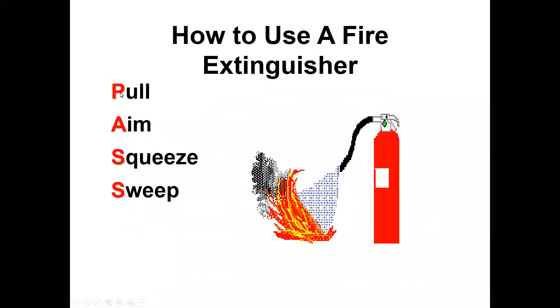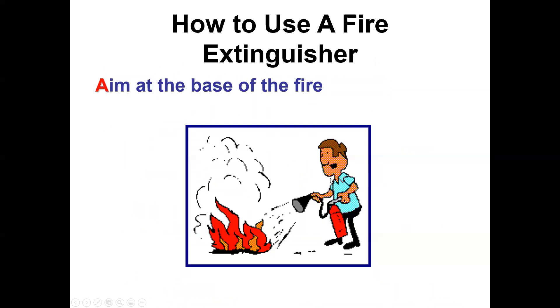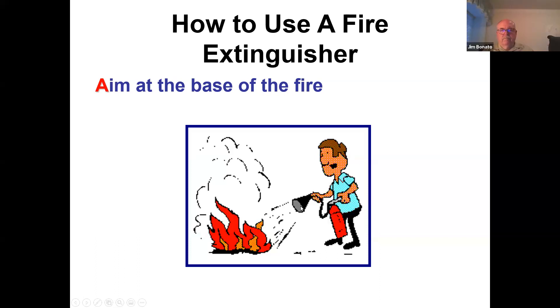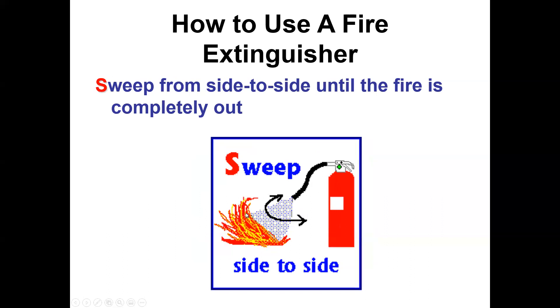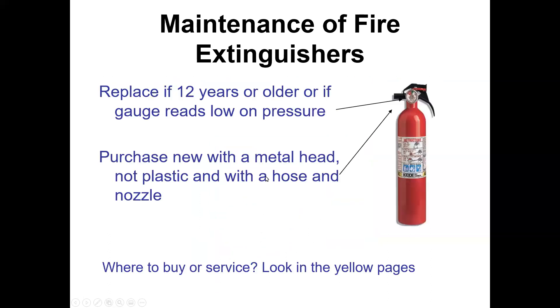The acronym for extinguisher use is PASS: Pull the pin, Aim the hose, Squeeze the handle to discharge, and Sweep the fire left to right — slowly, not rapidly — because you want to put the maximum extinguishing medium on the fire. Aim at the base of the flame, not the top. You can shoot into the flames all day and do no good. Sweep from side to side slowly until the fire is out.